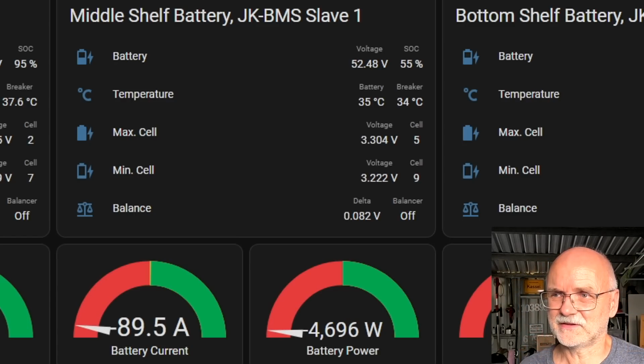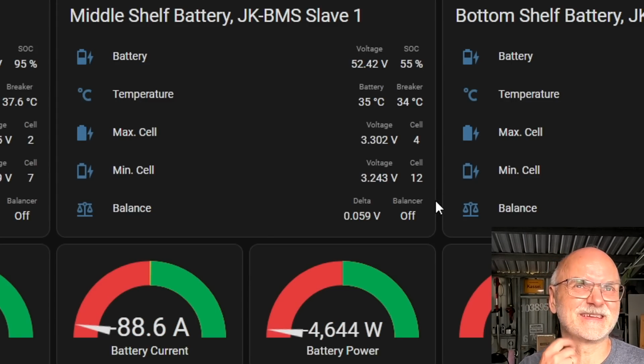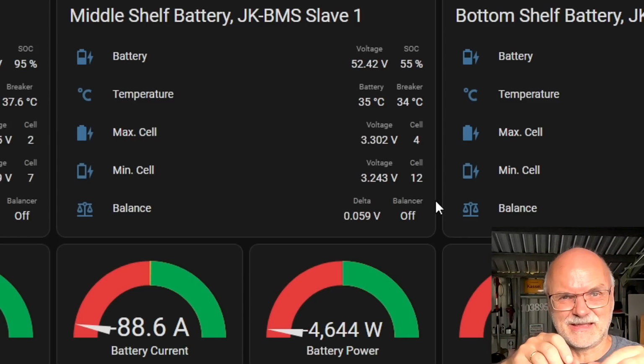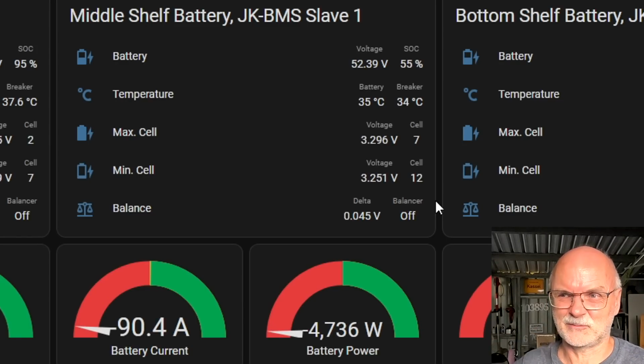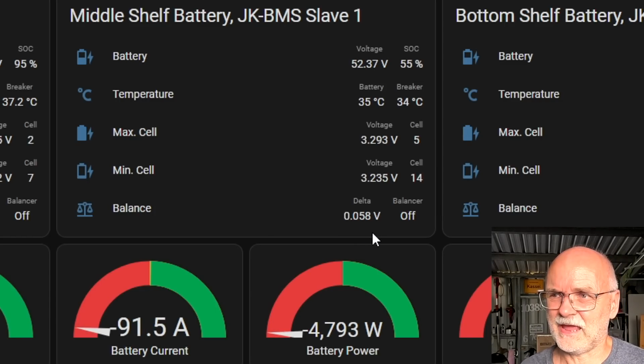Alright, so I reseated the positive. Minimum cell voltage is now at cell number 9, which is good, it's not number 16 anymore. Well actually, it's actually bad, because I just loosened the nut and wiggled the bus bar a little bit on top of the terminal and then retightened it with 4 Newton meters. And now at 5 kilowatts, we are seeing here 45 millivolt, 58.